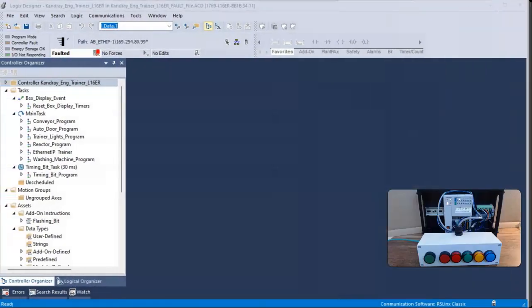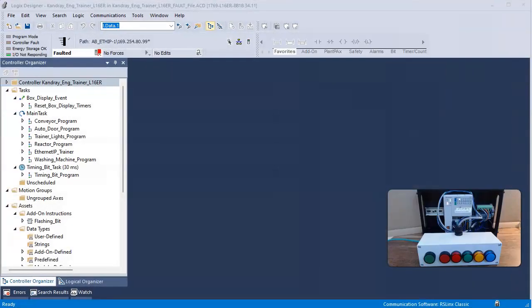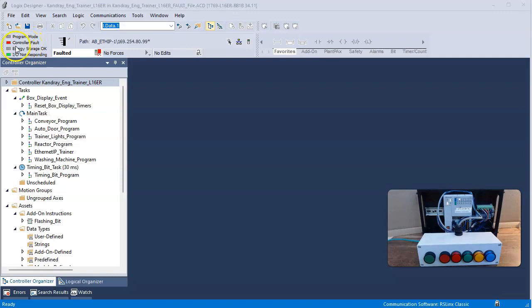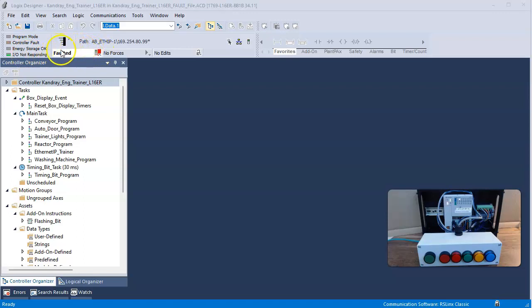So I've connected with the PLC and I can see that I have a controller fault, and it's flashing right here. And the IO is not responding, and I'm given the status of the fault that the PLC is faulted here.